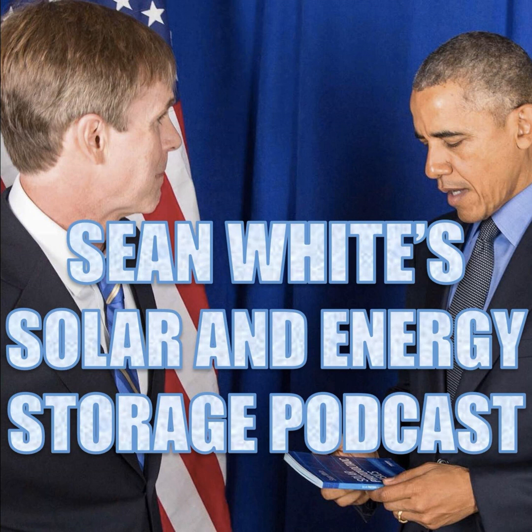And so let's get into some of this terminology. Ampere interrupting capacity. So it could be in kiloamps or in amps. A lot of times we're talking about kiloamps. So 10,000 amps would be 10 kiloamps. Interrupting capacity, that would be the maximum current that you could interrupt. So it's sort of like the breakers have a range. So it could be a 40 amp breaker, it could be between 40 and 10,000. And then maybe you'll have a main breaker on the supply side of that that's going to get those higher amps there. There's short circuit current rating, fault current rating, all this.